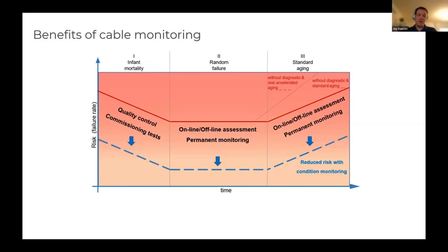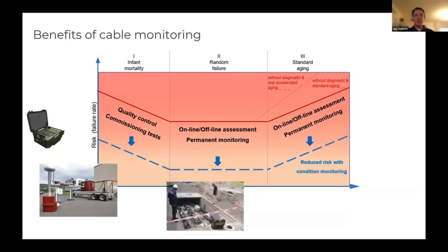And that's important because if you look at the US across the 600,000 plus miles of transmission cable, more than half are into their second half of expected life or useful life. But when we put cables into service, we often do a high pot PD test to identify and make sure that there's no PD or imperfections with the insulation on the cable. We do this with a resonant test set. And we're looking at the terminations and the joints connecting the cables. And we typically do this with portable PD monitoring equipment.